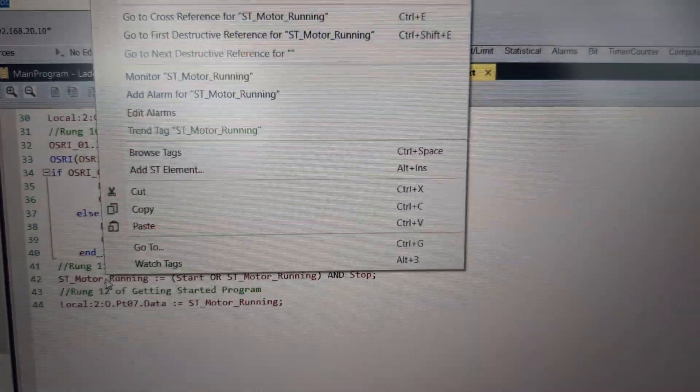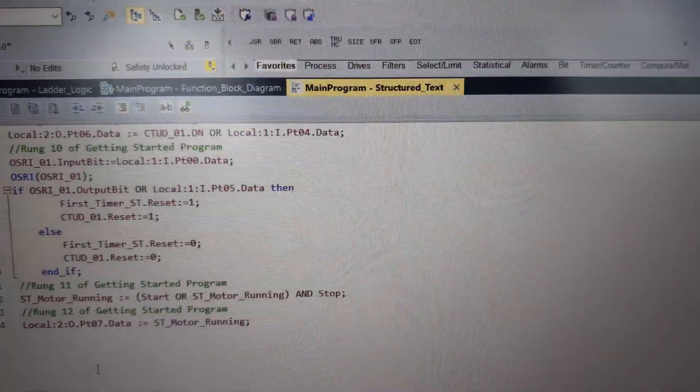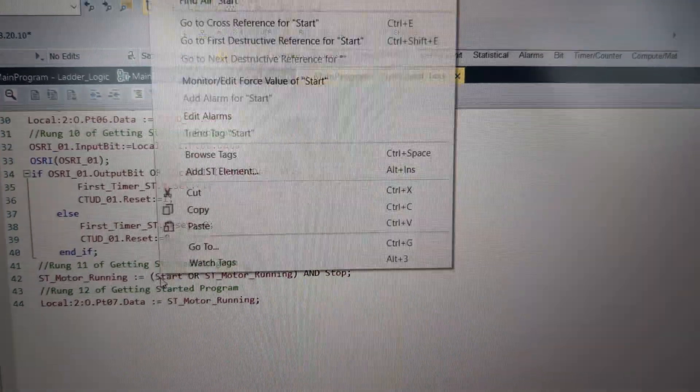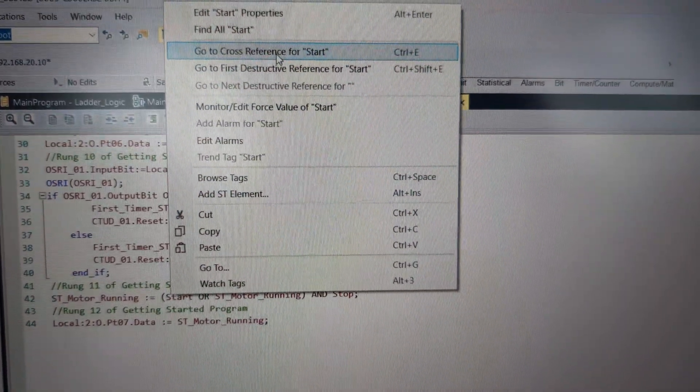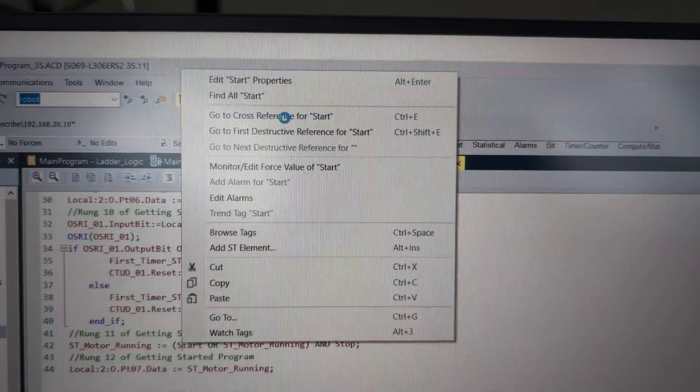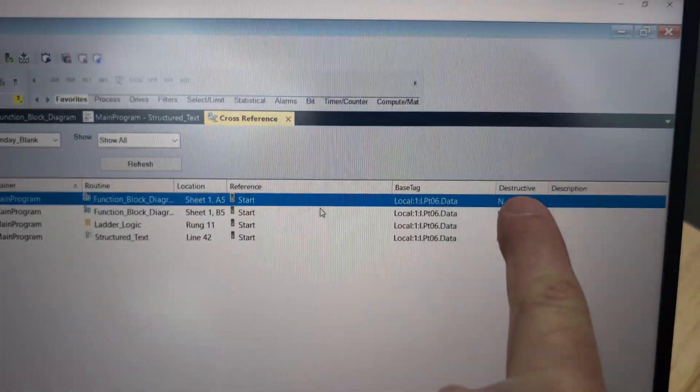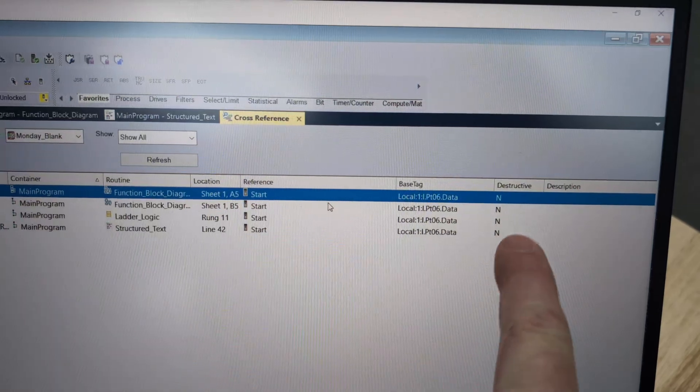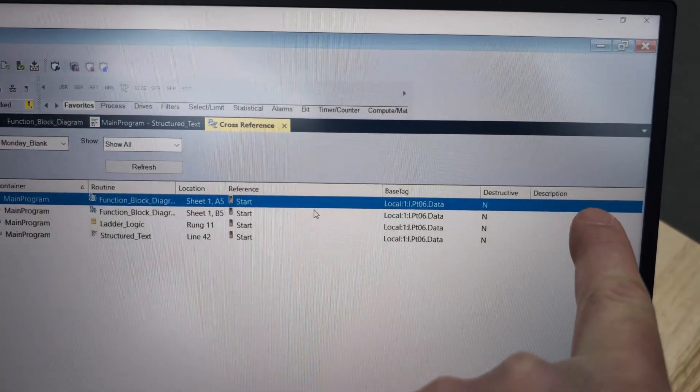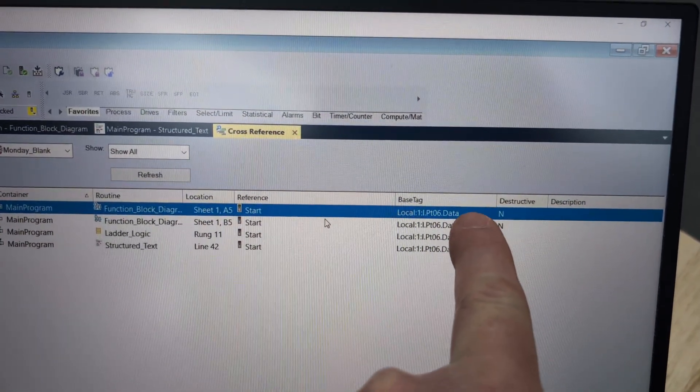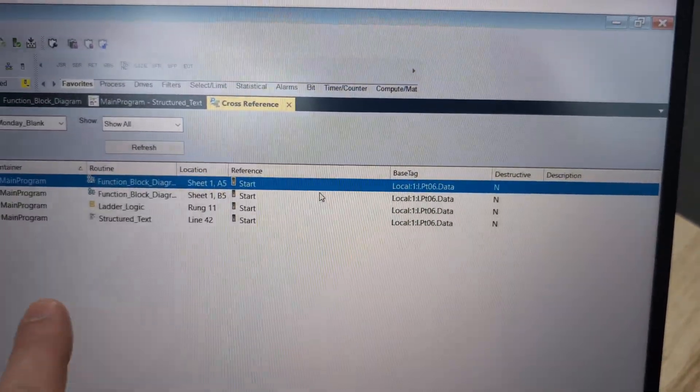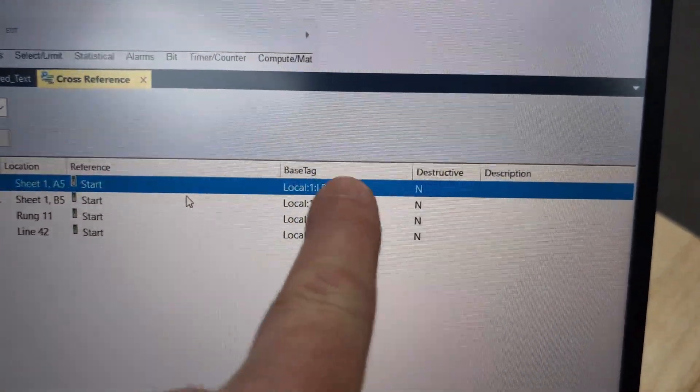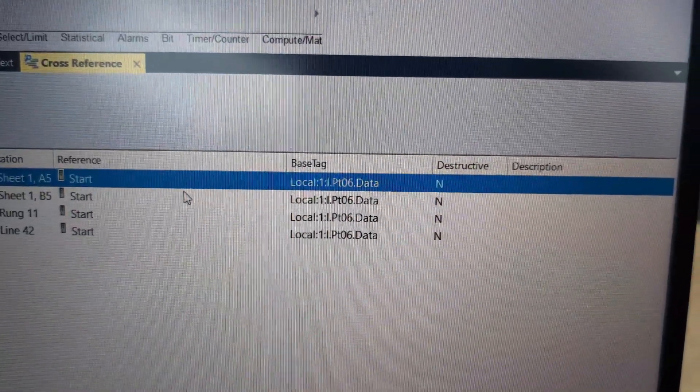Because you can't fully say we can't use aliases. There was some benefit through here. We right click start, because we want to know what the world's writing to it. And we go to cross-reference, and usually we're looking for a W. And here's what stumps people on them. A W is something is writing to this. Well, we have no Ws, and so we think nothing's writing to it. And here's where I always scream at them, take your hand off the mouse. Because we know this is changing somehow, and eventually that'll gravitate you to this base tag column, and there's where you would see it.